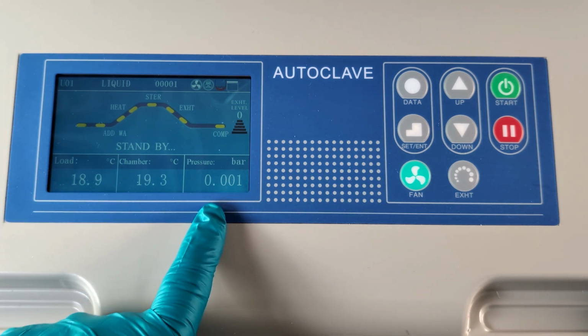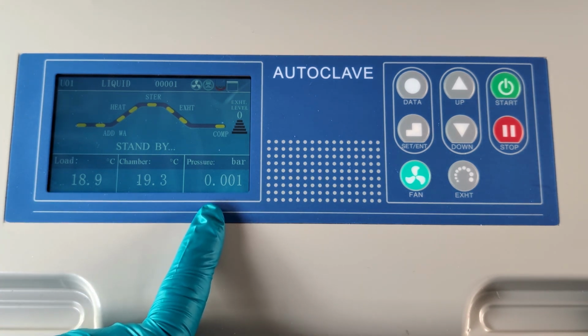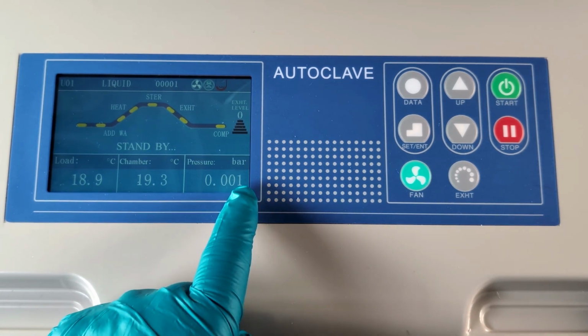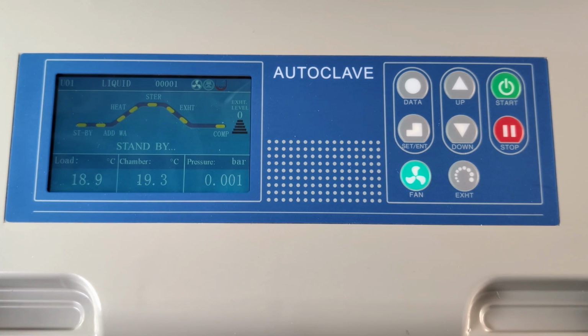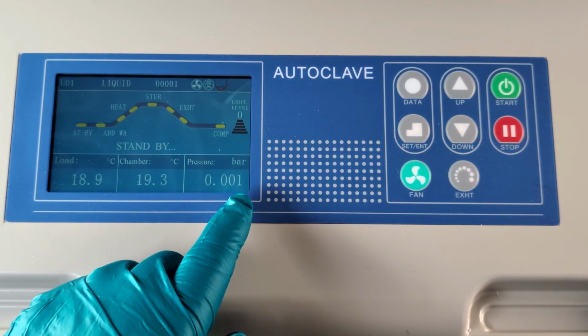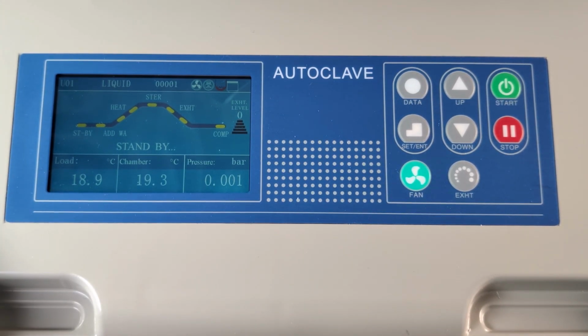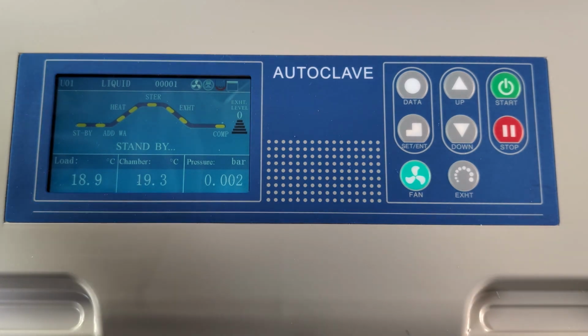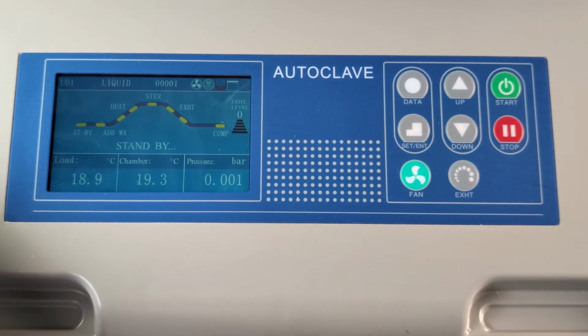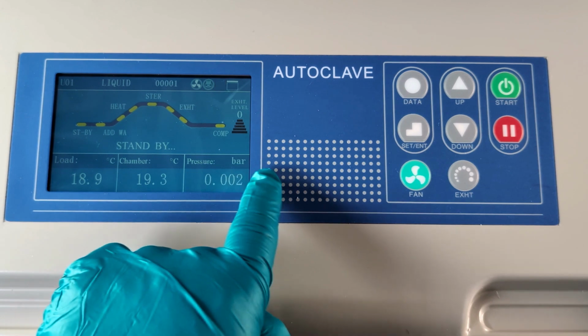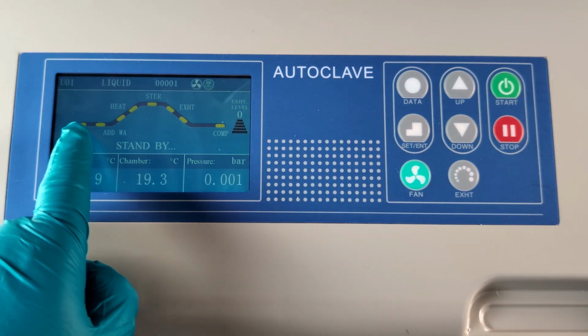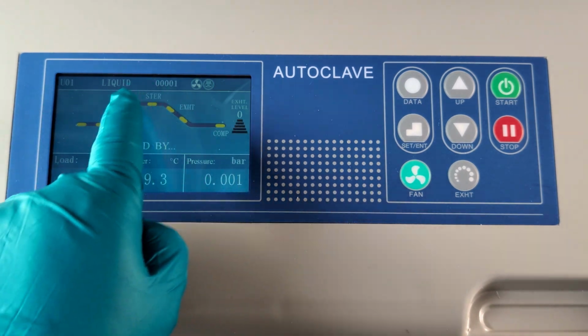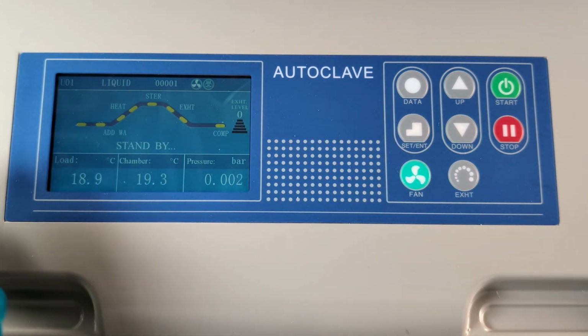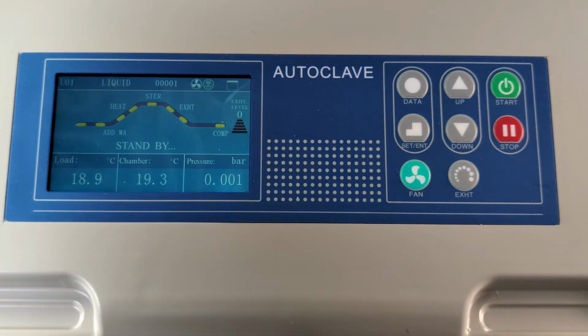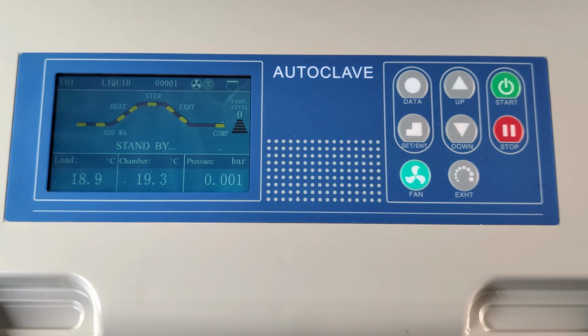This is what we call the gauge pressure. So it's the pressure over and above atmospheric. So at the moment, because it's just about 0, maybe slightly higher than 0, it means that you've got 1 atmosphere pressure. You've just got the same as we have out here. And so these are the 3 parameters you'll be looking at all the time, and this gives you a nice overview of how the program is running. So that's a quick potted description of what the autoclave controller does.